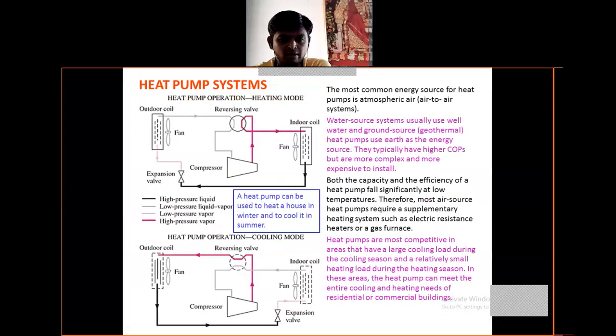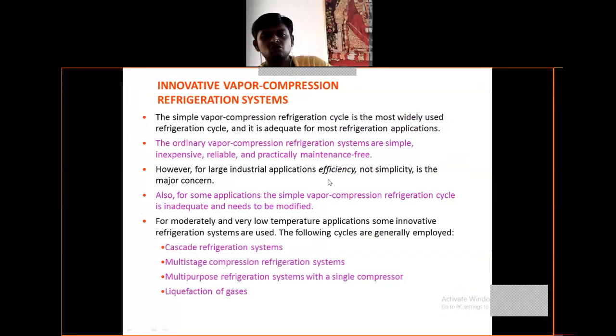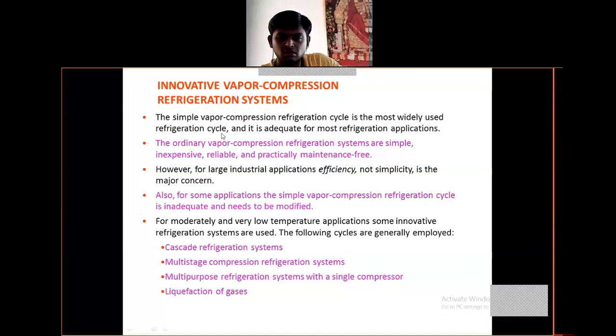This is the heat pump system in both cooling mode and heating mode. The heat pump can be used to heat a house in winter and cool it in summer. The black line indicates high-pressure liquid, gray indicates low-pressure liquid, pink indicates low-pressure vapor, and dark pink indicates high-pressure vapor. The ordinary vapor compression refrigeration cycle is the most widely used refrigeration cycle — it is simple, inexpensive, reliable, and practically maintenance-free.